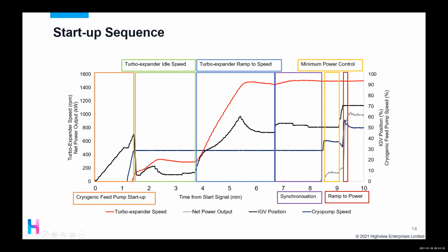So once this phase had finished, the variable inlet guide vanes opened. Again, the pump is still at minimum speed set point, so about 20 hertz or so. The variable inlet guide vanes open and the turbine ramps up to nominally 1500 RPM. Once at this point, we can enter synchronization. The variable inlet guide vanes are using precision control to allow the control system working with the generator to synchronize to the grid, so matching frequency and then phase and voltage. Once that occurs, we pull in the breakers and we're synchronized to the grid.